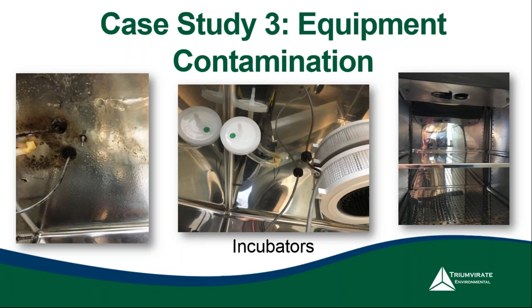You want to avoid using bleach solutions on these metals as it can pit the surface. Quaternary ammonia solutions, usually followed by a 70% IPA rinse, are often specified for routine BSC cleaning. Cleaning the water bath, refilling with distilled water, and using AquaGuard or a similar product will also help prolong the times between cleanings and maintain a clean incubator.